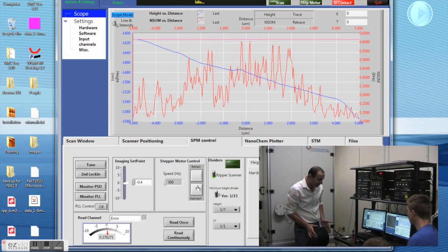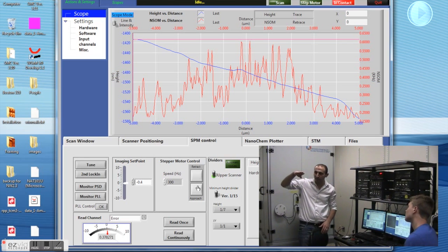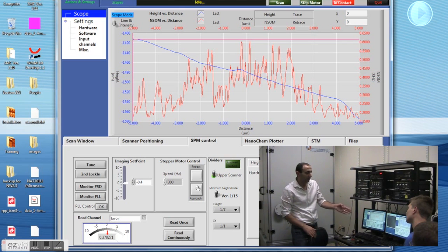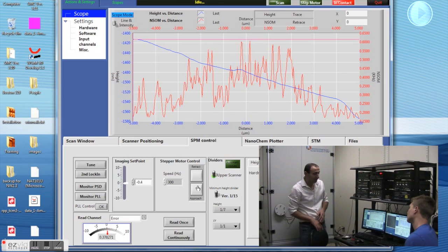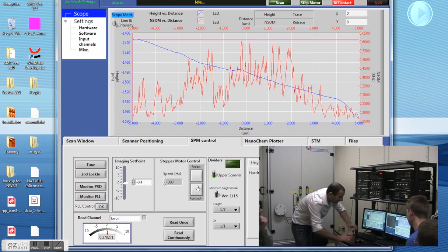But where's the tip? So this is the beauty of the tip. This is a small, little point. So just keep in mind you have the standard silicon cantilever with the pyramid apex going down. So you will not be able definitely to see such a thing. Now this is true for AFM tips, for NSOM tips, for thermal tips, for electrical tips. You can easily have them exposed, so you can combine AFM with optics easily from top and from bottom. And you can combine AFM with other modes of SPM operation easily with this type of access, accessible by multi-probe, for example.